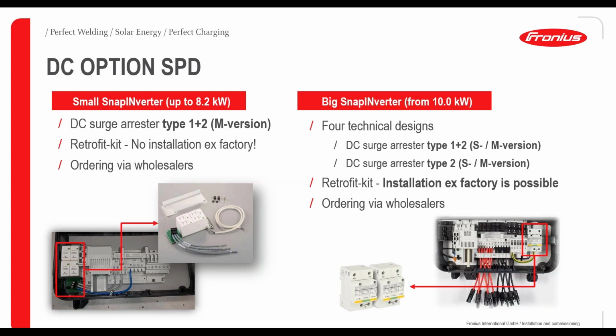There are options also like on the Gen24 to integrate the SPD within the wall bracket. As we now saw, there is the option for the big SnapInverters, so the big Symo and the Eco from 10 kilowatt on, to do it on a DIN rail mounting. We can see it on the picture below. It's just mounted on a DIN rail, and the cable connection will be done then on top on these screw terminals I just mentioned. Actually, there are 4 technical designs. Either you want to use a type 1 and 2 or just type 2 for single MPP or multiple MPP. You can also have it ex-factory, so pre-assembled, or you can do it yourself with a retrofit kit. That's only possible for these big SnapInverters for the DIN rail mounting.